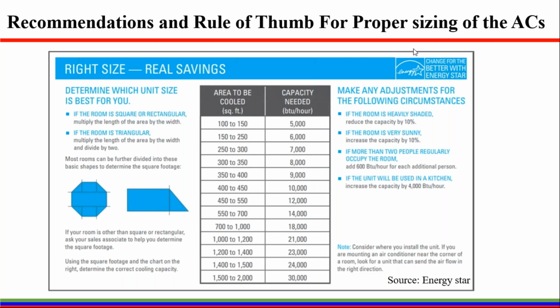And here it is shown that if the room is heavily shaded, or the roof is shaded with something else, or it is a double story building, then you can reduce the capacity by 10%. And if the room is very sunny, you can increase the capacity by 10%. If more than two people are there, you can increase by 600 BTU per hour for each additional person. So the requirements are given here. It is available on the Energy Star website also.